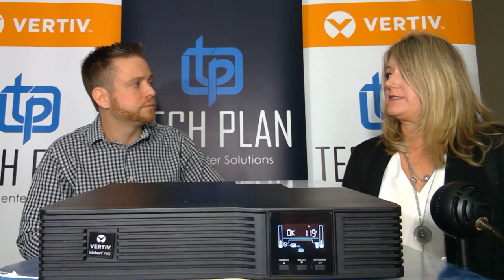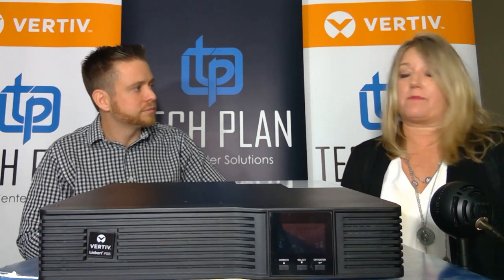There's obviously an audible alarm from the unit. My phone is vibrating in my pocket — that means I've just got an email notification because this is connected to the web. In the background, the NOC in Columbus, Ohio will be notified this unit is now in alarm, so they'll be trying to remotely diagnose the issue, see if they can power cycle it, contact you if need be, and dispatch a technician. Now I'm going to plug the unit back in — it's now back on utility power. My phone just vibrated again with another notification. This is now running back on utility mode. We're going to keep letting the battery die so we can demonstrate what happens when the battery is fully depleted.